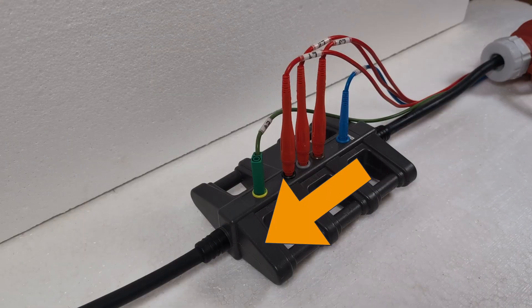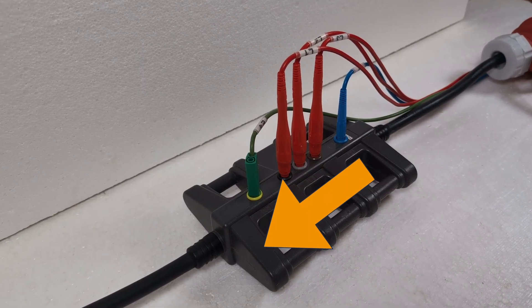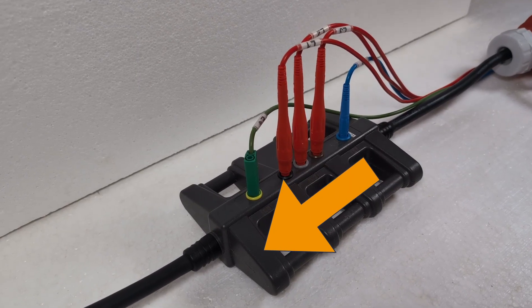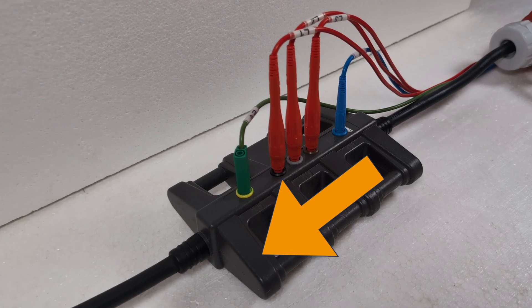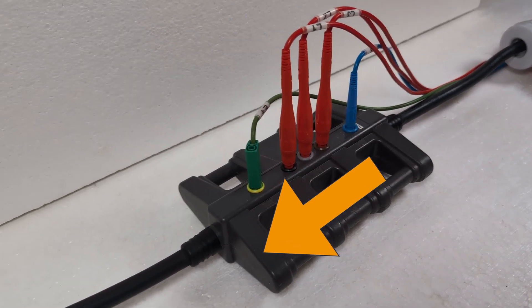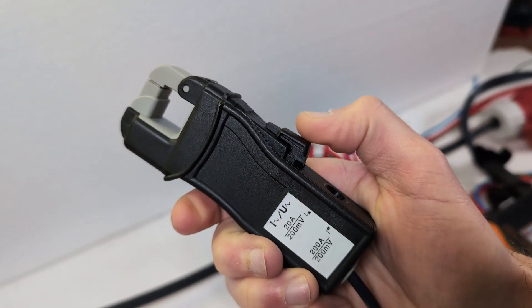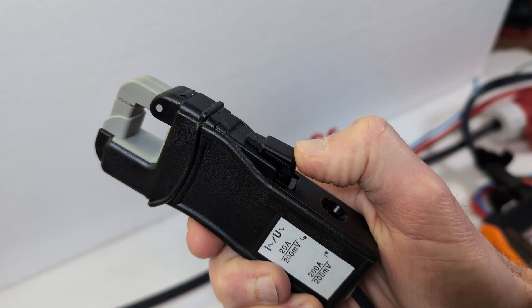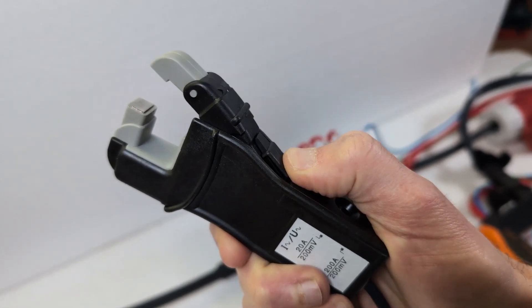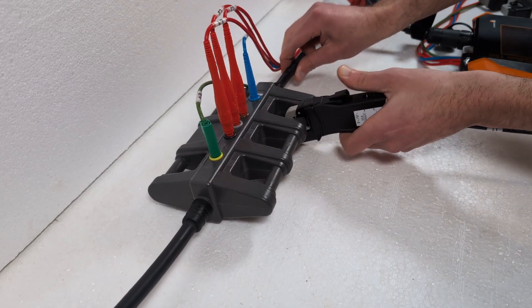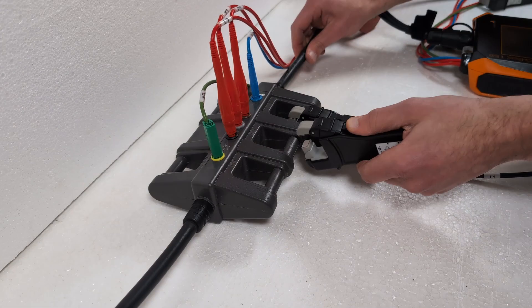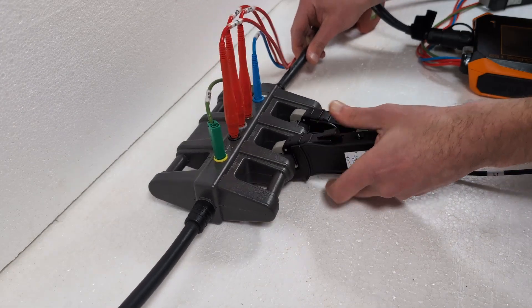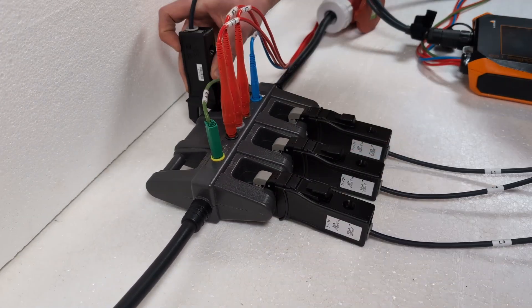The arrow should always point towards the system of the electrical consumer, even for the neutral conductor. I open the clamp by pushing the slider forward and place the clamp on the corresponding measuring tab. I do this with all four current clamps.